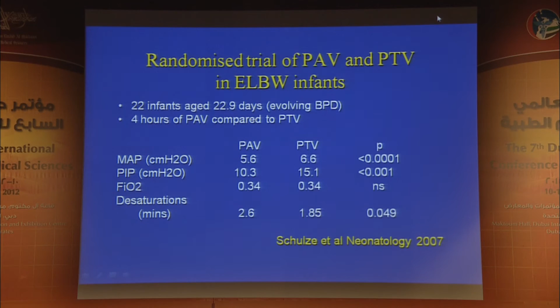Andrew Schulze has published 2 clinical studies, both with the same design. They're crossover studies, one in acute RDS and one in infants with evolving BPD, which I show you here. They both have the same message. The blood gases were maintained, as shown by the inspired oxygen here, at lower pressures on PAV than PTV, suggesting it's better. But there were a greater number, and therefore longer, desaturations on PAV, showing that the backup rate and the setting of it is critical.